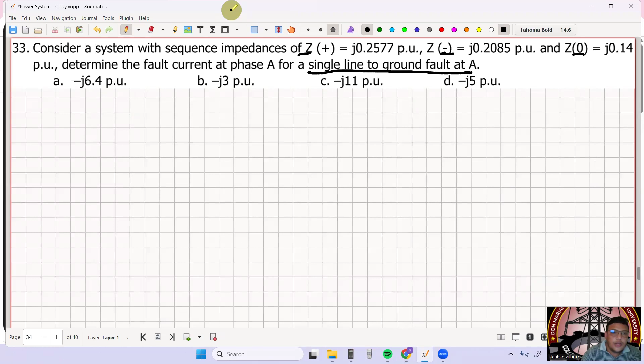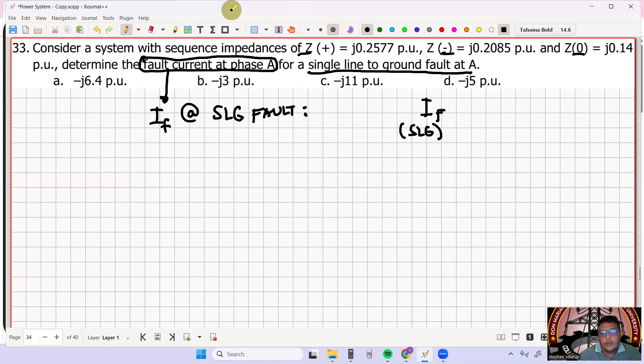So meaning phase natin to, okay? Or tama, fault current, overall fault current. So yung overall fault current natin at phase A, at single line to ground fault. So from our generators or AC alternators na formula, pwede natin siyang i-apply dito. Okay, so that your I fault for a single line to ground is equal to 3 times IA1. But what is your IA1 for a single line to ground fault?